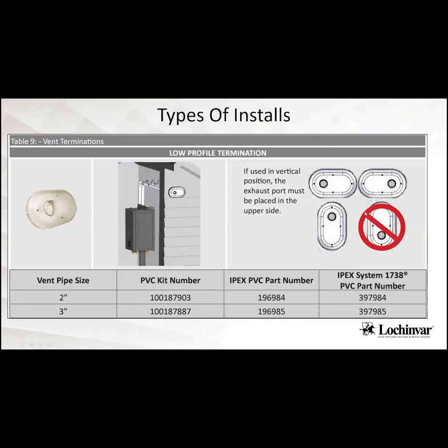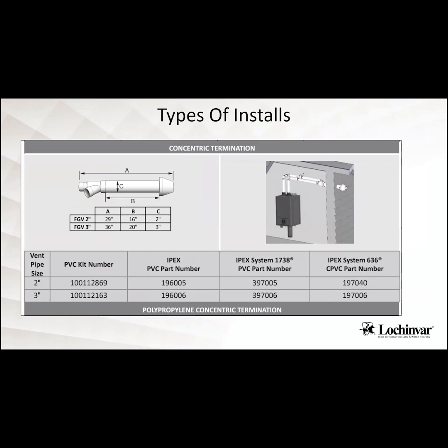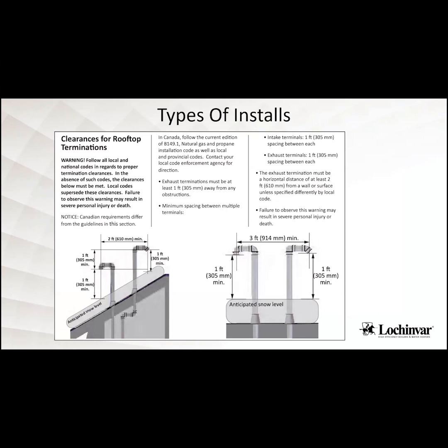Also make sure that you are not configuring it this way because you will start sucking in flue gases if you have it upside down like that. Then there are other concentrics, the bazooka concentrics, you can use those as well. Just remember that your exhaust is the middle and your intake is off to the side. If you are going up with 2 pipes out of the roof and your exhaust is above your intake like this, you only need to be 2 feet apart. If you're coming out of a flat roof and they're on the same level, then they need to be 3 feet apart.